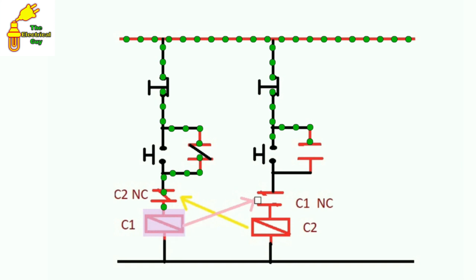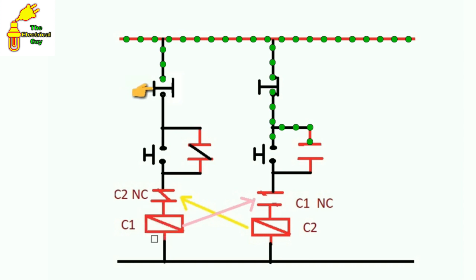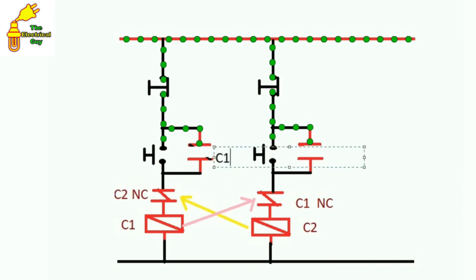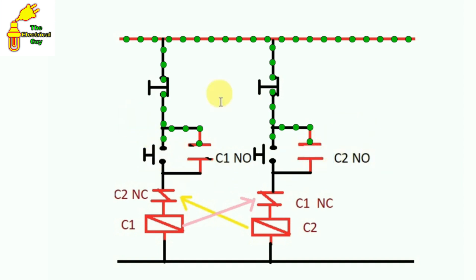Current flows from here. If we release this push button, it goes back, but this auxiliary contact is now NC so current is flowing from here to the contactor and this contactor remains picked up. But along with this, when C1 contactor is on, the C2 side becomes NO — this power supply line is open from here. Now even if we press this start push button for C2, current will not flow further because it is open from here. This is why both contactors cannot be turned on together. Till the time C1 remains on, C2 will not become NC.